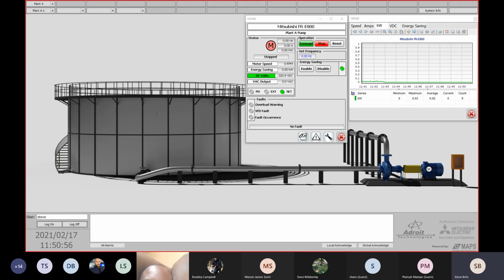Yeah. Adding on to that, we have 2 big fans, 1.1 megawatt motors, running with big VFDs. Sometimes we run them at 35 hertz without full frequency. Now the current drawn by that full load motor will be reduced, even the kilowatts. The power consumption will be less when you pay the bills. Yes. No, absolutely.